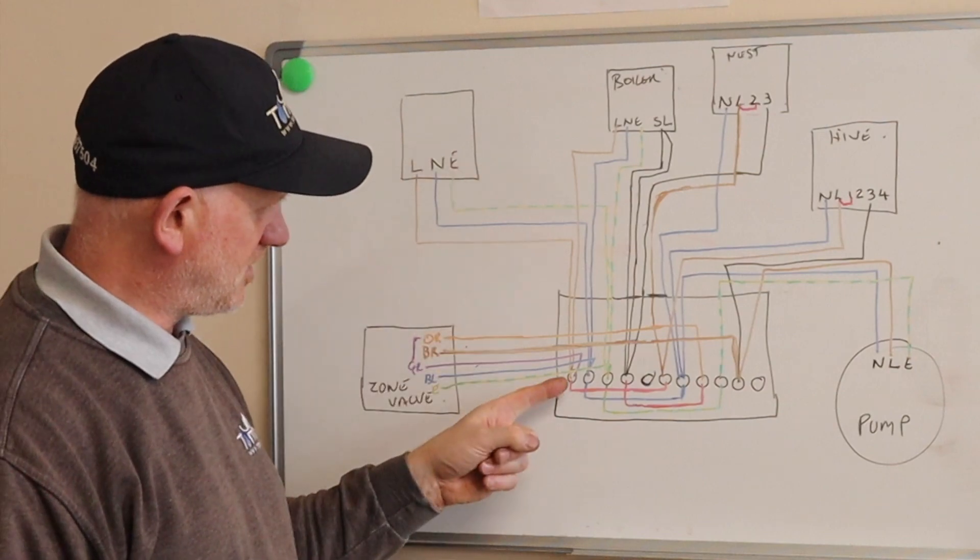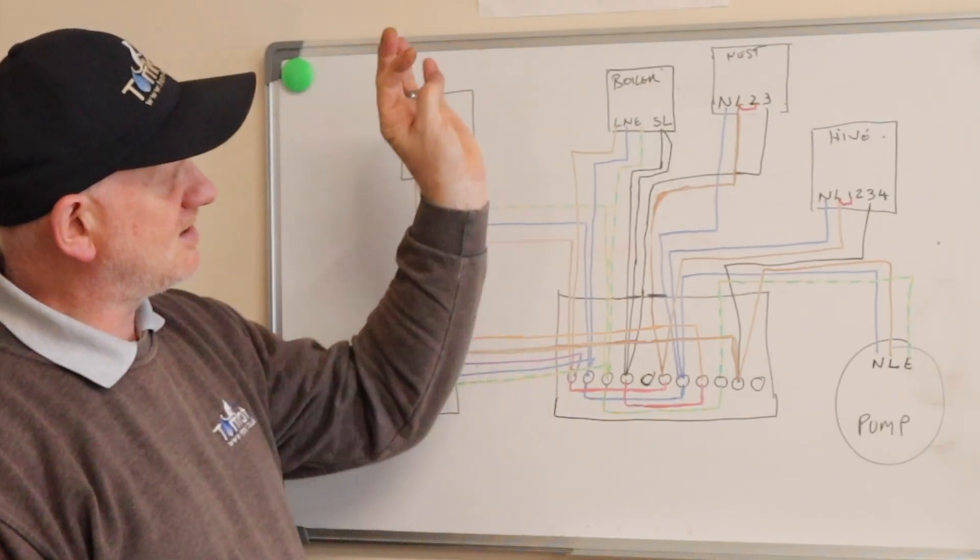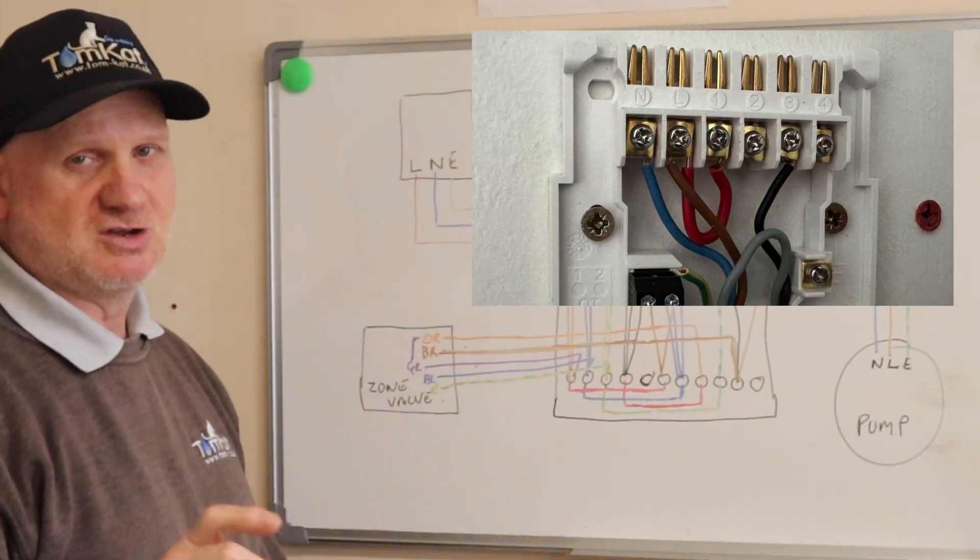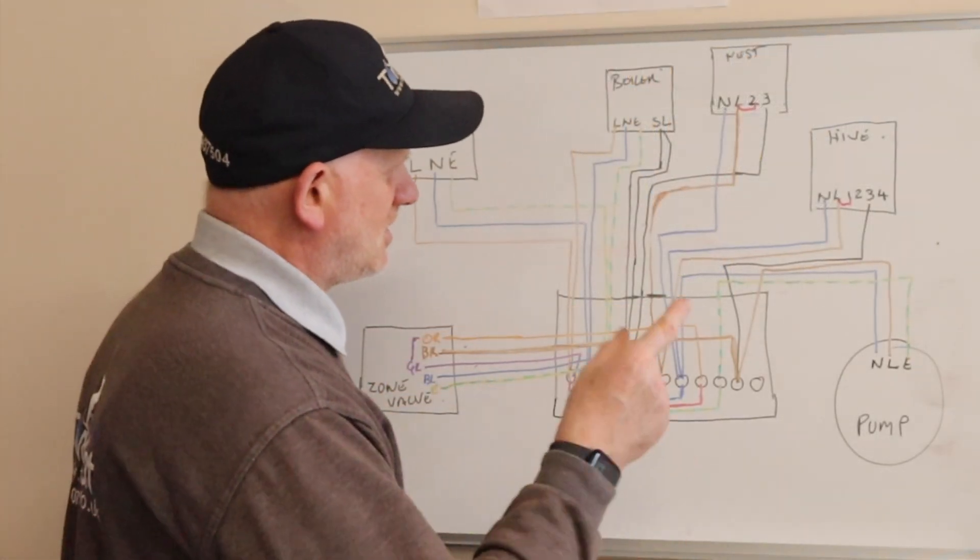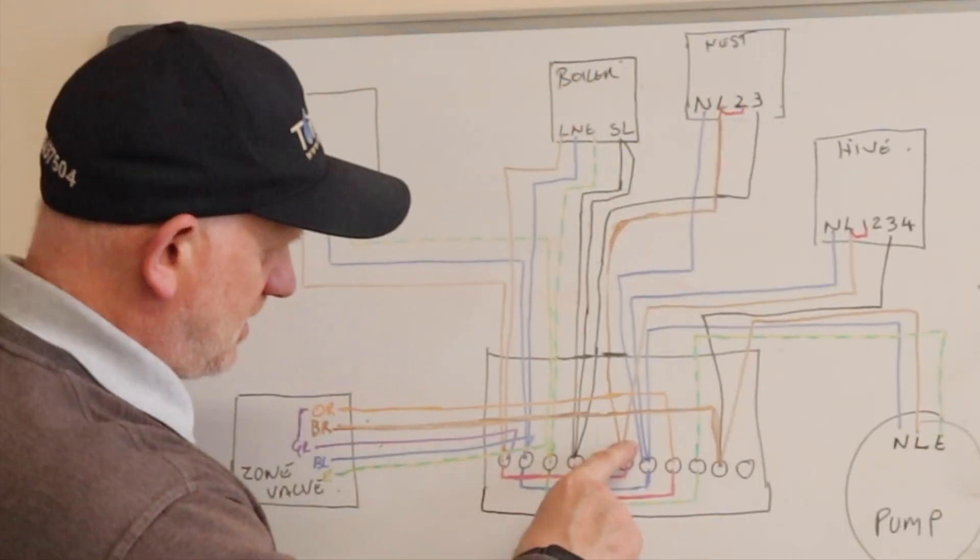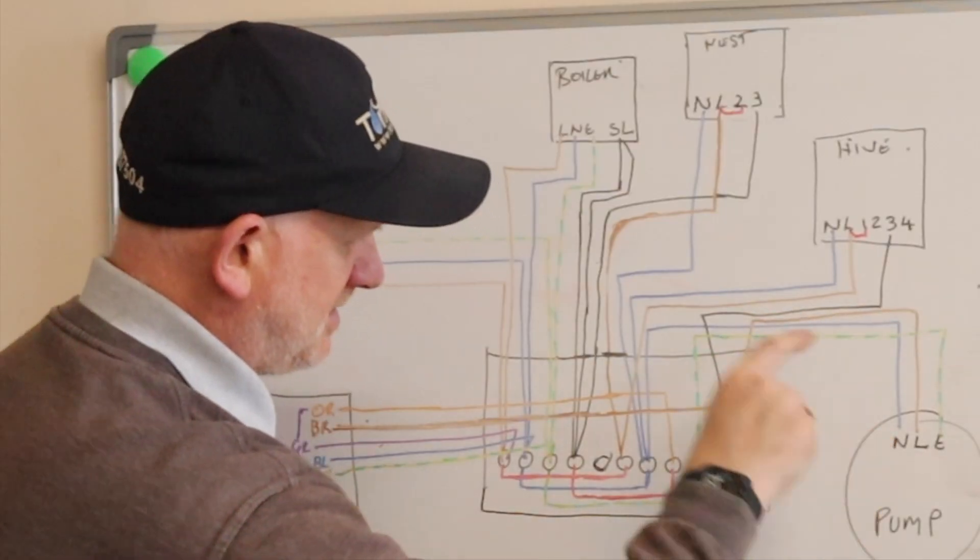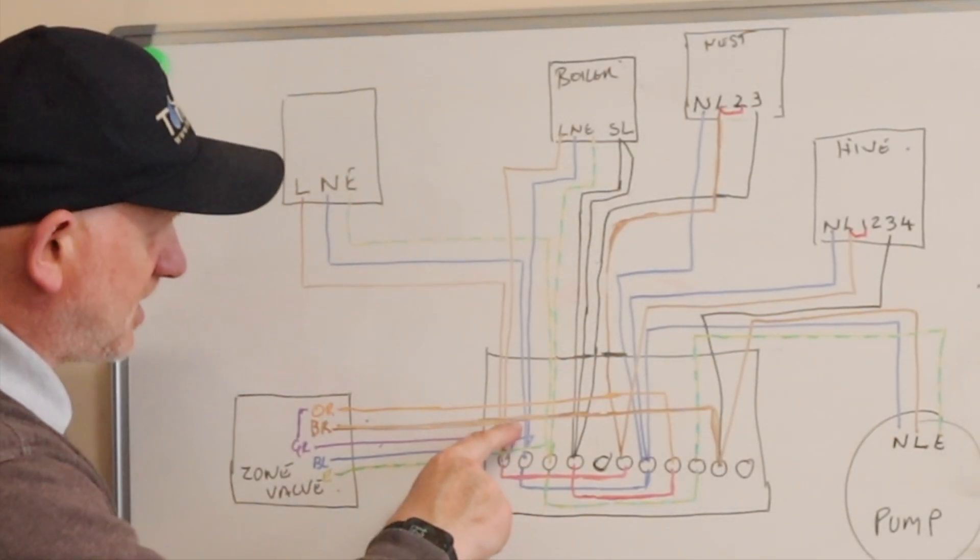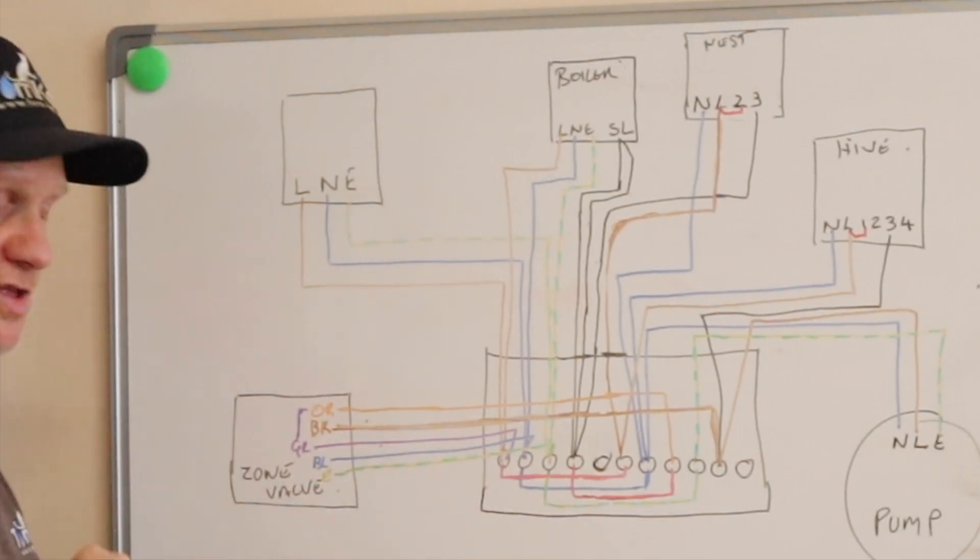All I figured out was what was the live, neutral, and earth going up to the boiler and what the switch live was. I've put live, neutral, and earth into these first three here. The hive required a live and neutral. There's also an earth connection there which I didn't use because it's plastic and it doesn't really need it. I used links so I wasn't trying to cram all the wires into the same block. This is the neutral here so it's feeding the nest, the hive, the pump, and the boiler.